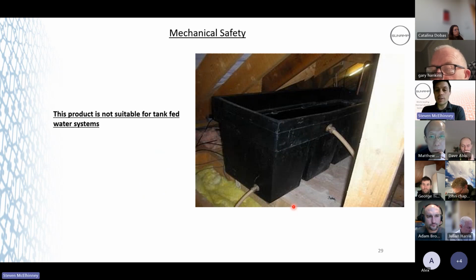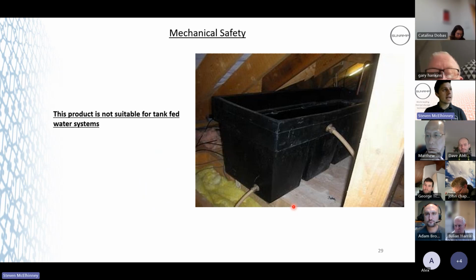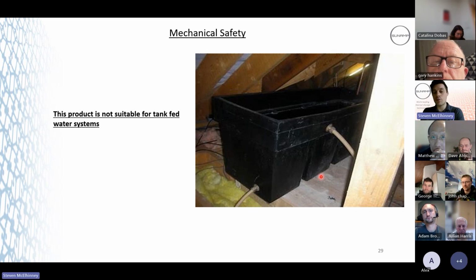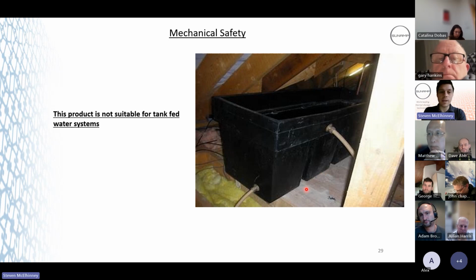The product's not suitable for tank-fed water systems, so we're converting from tank-fed systems to mains pressure. So this is quite important when you're doing your specification of a house. Does the customer have enough mains water? High enough pressure of mains coming into their property? Because I think most water companies set the standard at a bar minimum that they'll ensure is coming into the property. So just bear that in mind. If the customer's at a ground floor flat, for example, and they've got a cold water storage tank up in the attic of that apartment block, they might be getting about 1.5 to 2 bar possibly. You convert that to mains, they might get less. So it's just something to bear in mind.